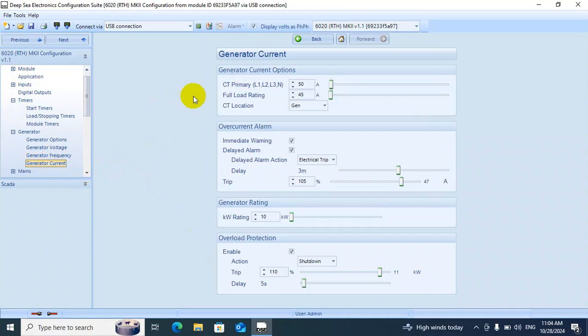This is the generator current option. We will choose the current transformer. We'll see how much the current transformer is and add it here, 50. And for the location of the current transformer, we sometimes have to choose. We are fixing the panel on DeepSea also with the CT to another panel, to the totalizing panel or another panel. Then we have to choose the location. Now it's mounted on the generator. We'll keep it like this.